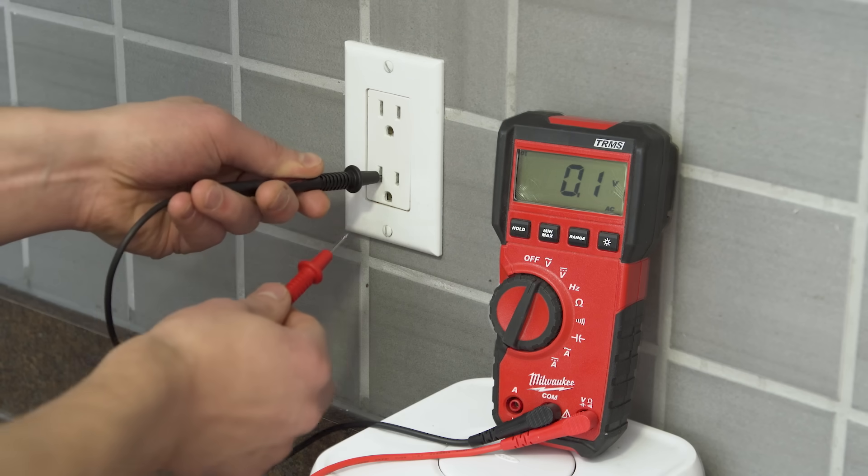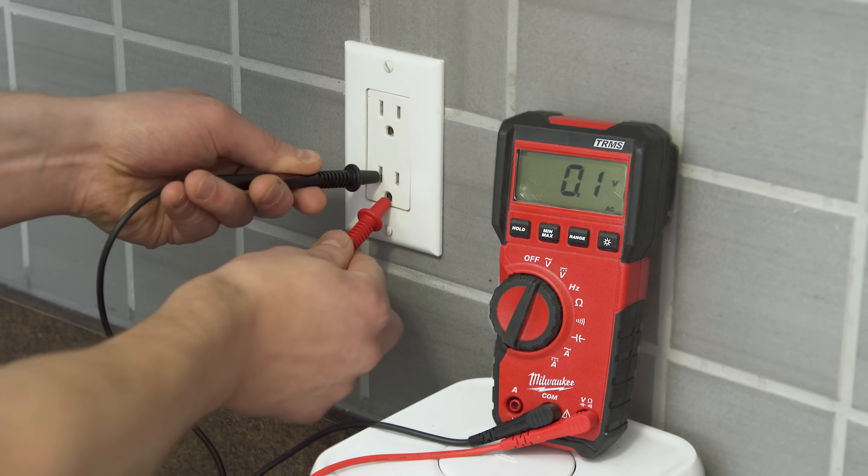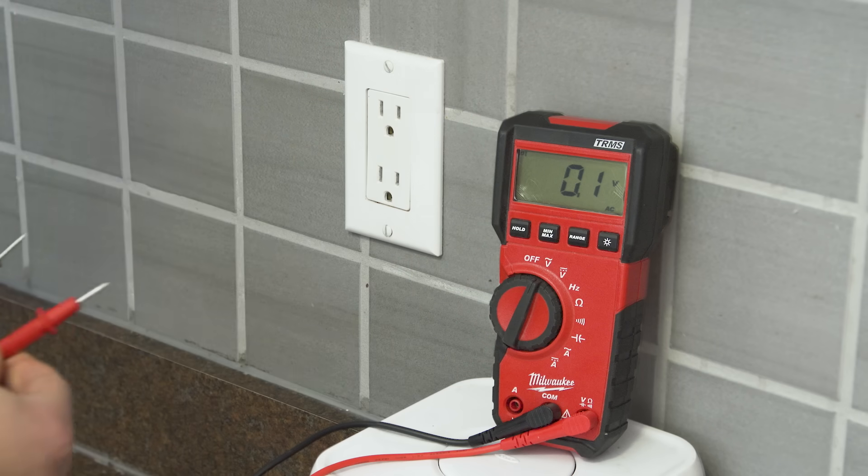When testing from neutral to ground, there should be no significant reading. If there is a 120 volt reading, then the receptacle might not be wired correctly, or there could be a short in the circuit.